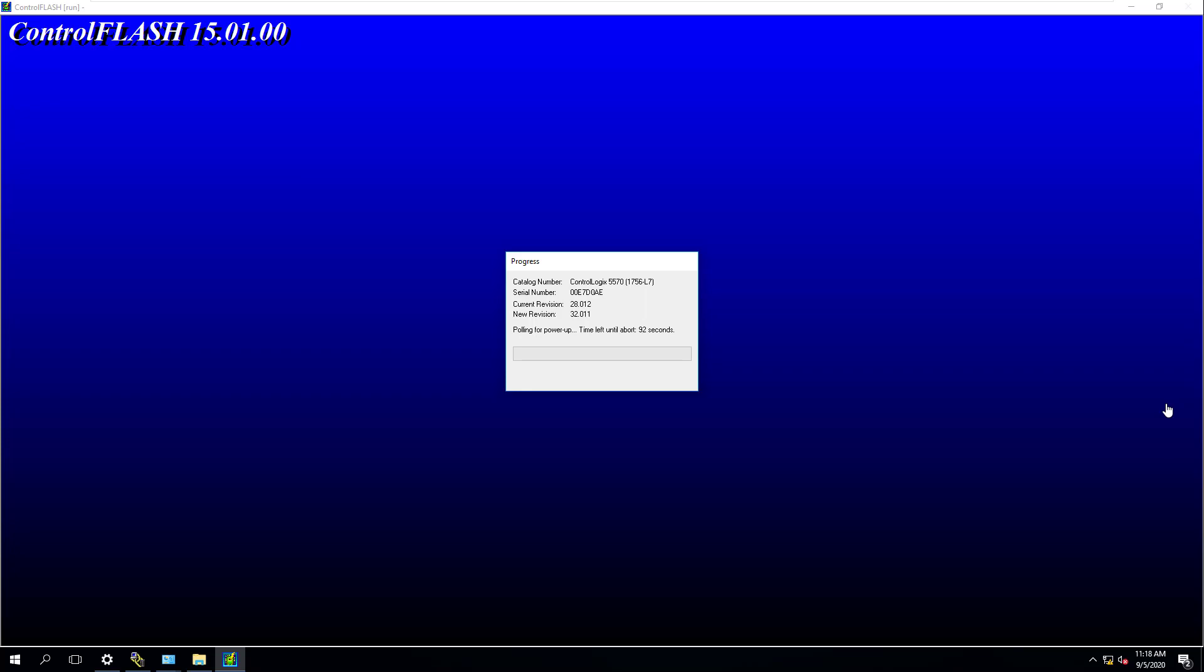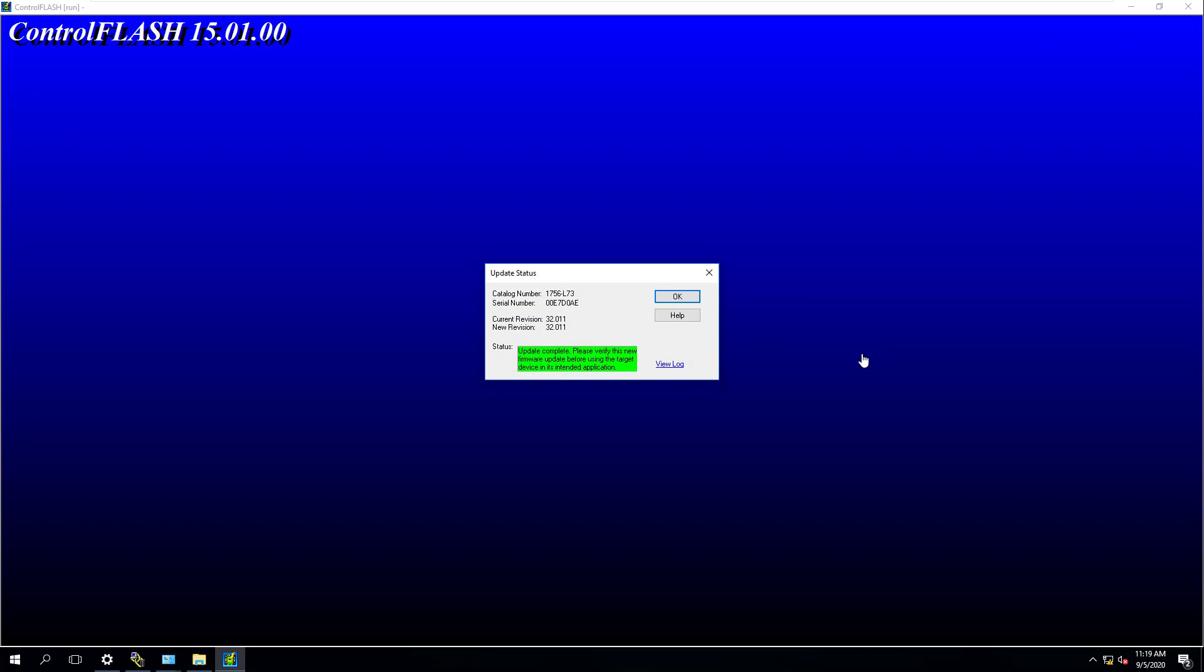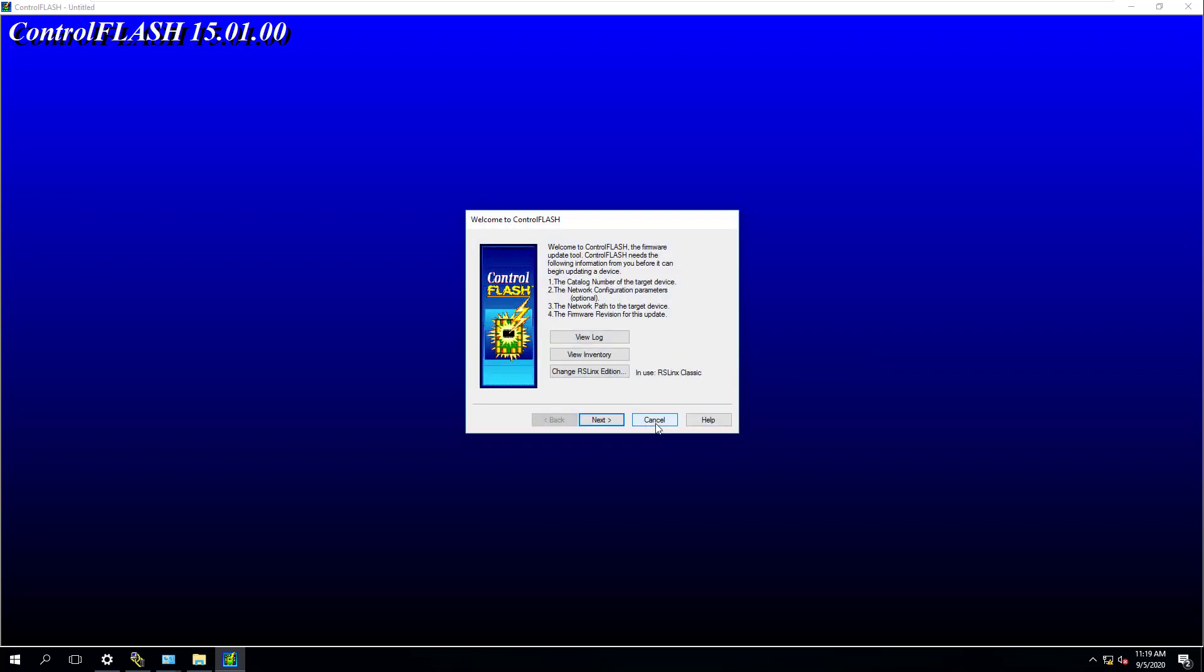Now it's polling, it's coming back and it's going through the process right now and it's actually coming through and making sure that it's power cycling, making sure everything's good, coming back, and then we're going to go into RSLinx and verify that it did change. Because again, once we do stuff, we need to have the due diligence behind what we're doing to verify that this stuff did actually transition because that the whole purpose of what we're doing is to take this L7 from a version 28 to a version 32 so we can start using it on our trainer to train with version 32 and as you see, we did actually have a complete successful firmware flash.